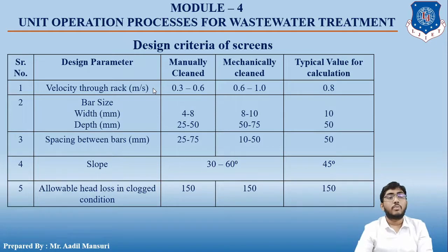Okay, next one is the bar size. Width for manually cleaned is 4 to 8 mm, and depth for manually cleaned is 25 to 50 mm, whereas in the case of a mechanically cleaned screen, width is between 8 to 10 mm and depth is between 50 to 75 mm. Okay, and typical values are 10 to 50.